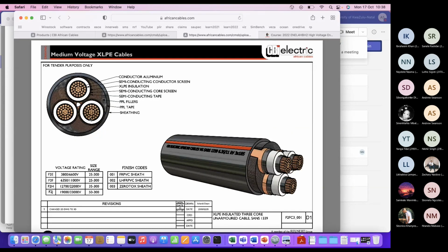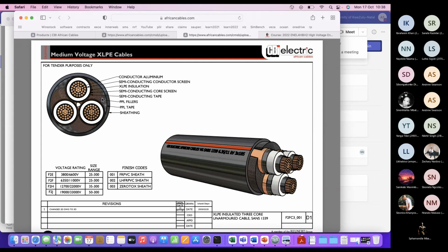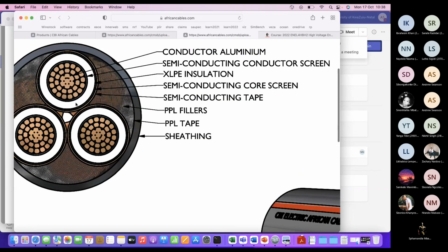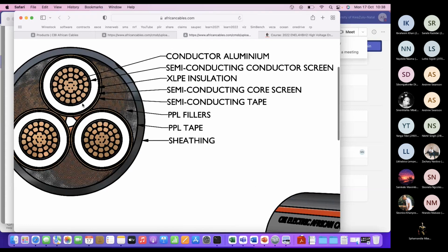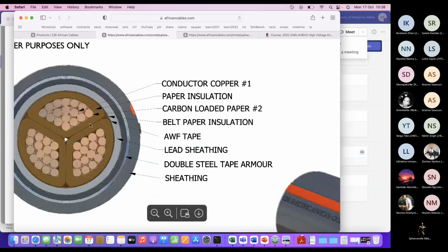And you can see there's 3 of them. And then there's lots of fillers just to hold them in place. So this one is purely solid dielectric. There's no liquid involved here. They offer different advantages and different disadvantages. If you think of a little hole in this insulation, a void, that void is not going to be covered by anything. So that void may end up going into partial discharge. It may end up getting eroded. If you think about this one, if there's a little void in that paper, it's going to be filled with oil.